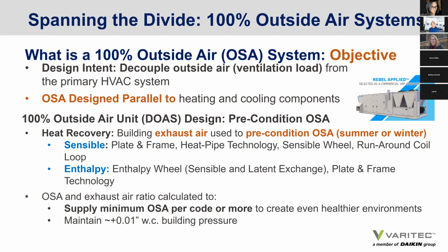So 100% outside air systems more often than not use energy recovery, and they come in two forms: sensible energy recovery and enthalpy energy recovery. And when you look at a 100% outside air system, you want to make sure that the exhaust airflow rate is below the supply airflow rate to maintain a positive building pressure, so you're not sucking in cold or hot air, depending on your season, into a building due to a negative pressure of the building. And both the exhaust and supply air of your outside air is brought through a common unit separated by a dividing wall with a heat recovery device. Either it's a sensible plate and frame device or an enthalpy recovery wheel, and there's even enthalpy plate and frame recovery devices available today that are very compelling.